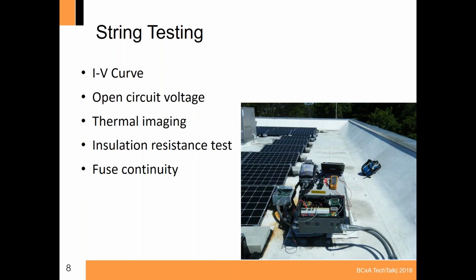For string testing, again, as part of the commissioning, everyone has a different definition of commissioning, but in most cases it will include all or most of the following, and these are basically electrical tests. This is something where this level of detail is going to be very accurate, but it also has an associated risk. So it's important. We use licensed electricians for this application. We follow NFPA 70E for safety equipment. It's important we wear our voltage-rated gloves, glasses, arc-rated clothing, and so forth.